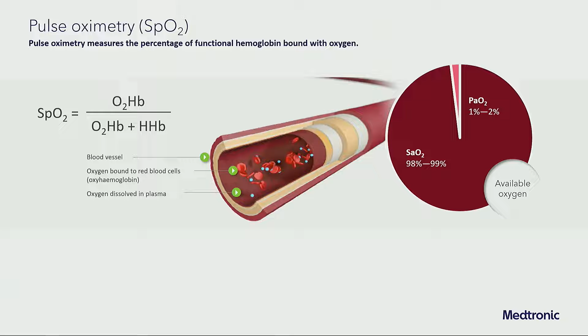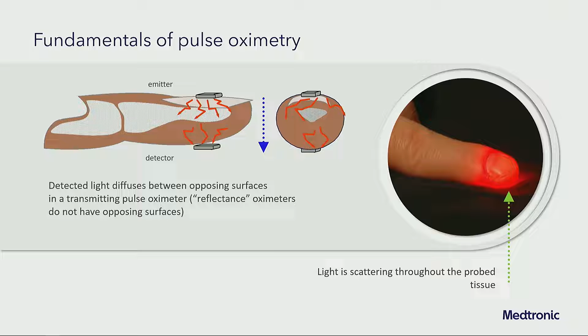What are the fundamentals of pulse oximetry and how does it work? So there are a couple of different types of pulse oximeters. There are transmitting pulse oximeters and reflectance pulse oximeters. Most of us are used to the transmitting type, where you have an emitter and you have a detector. So we're showing our finger. This is the one we're most familiar with. So you've got light going from the emitter being picked up by the detector. The light's diffusing through the tissue, and the detector is picking up the difference in light.